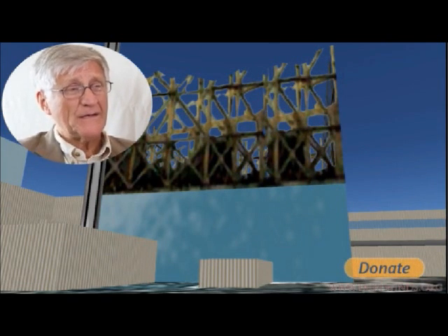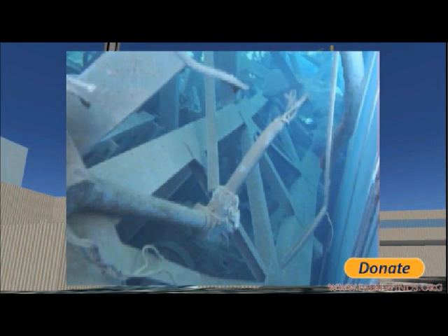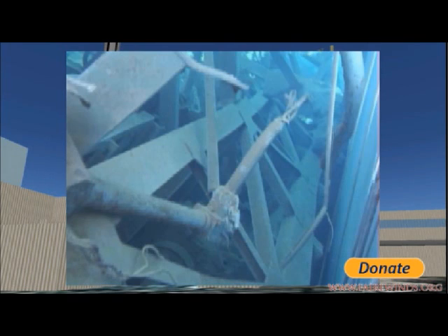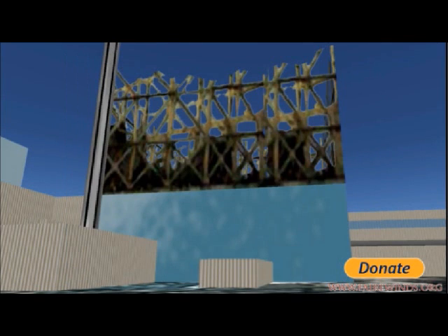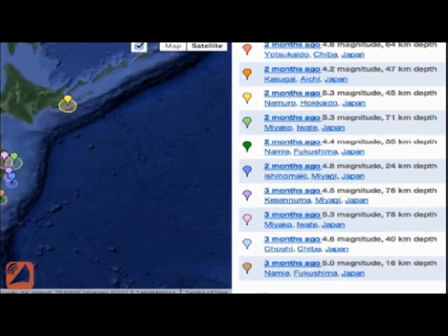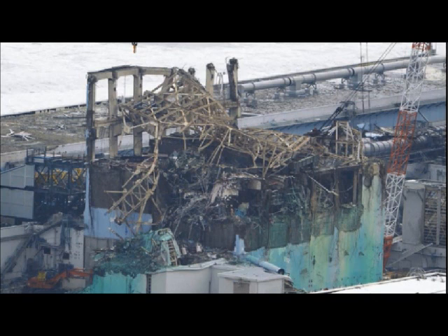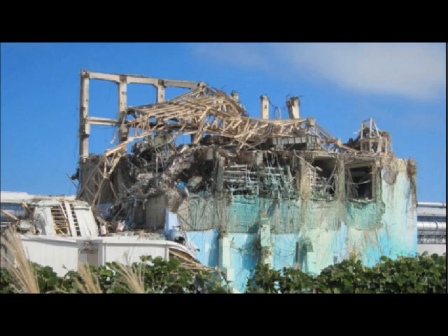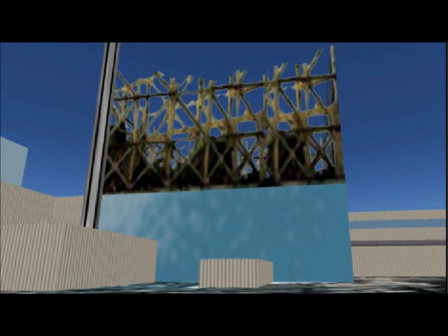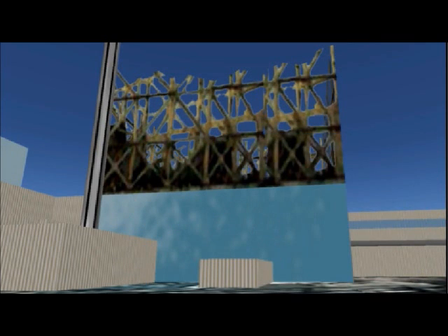So what will they do with Unit 3? It has fuel in the fuel pool that eventually has to be emptied, but radiation exposures are so high that personnel access is really limited. My biggest fear on Unit 3 is that another earthquake will happen — it doesn't have to be a Richter 9, even an 8.5 aftershock could cause this badly damaged building to topple and shatter. It's being covered and will probably be completely covered with a shrink wrap cover by winter, but right now it's the only building exposed to the atmosphere.